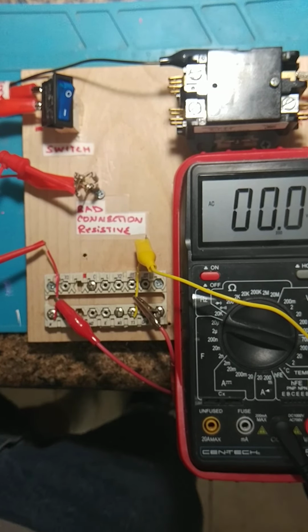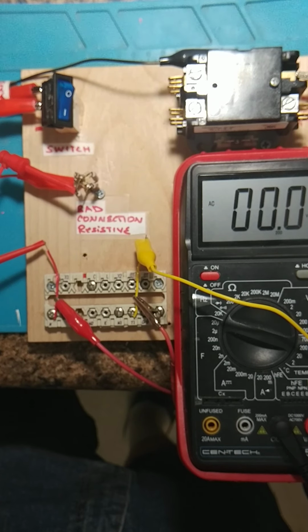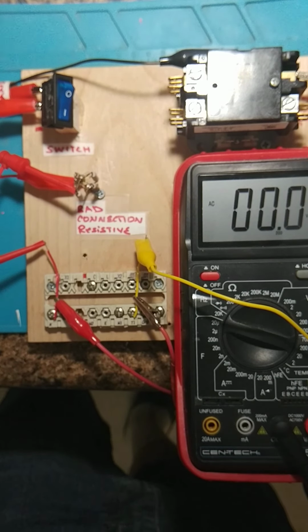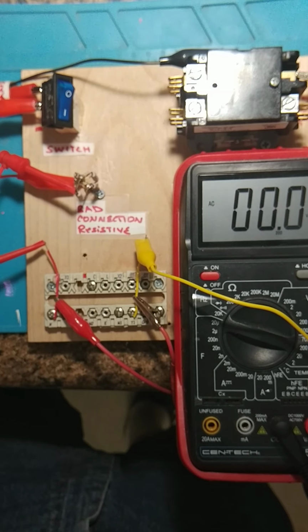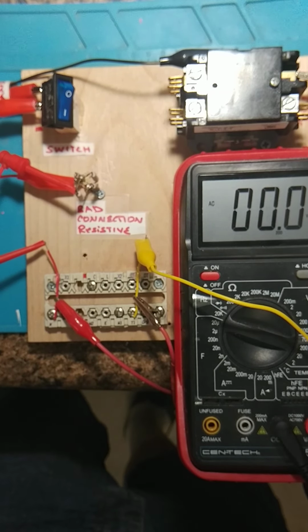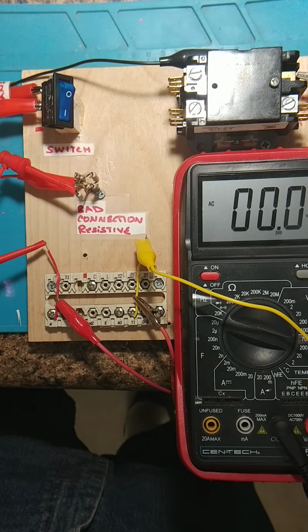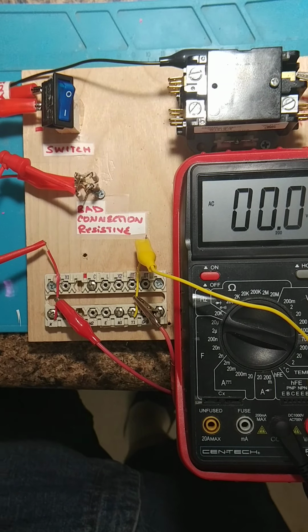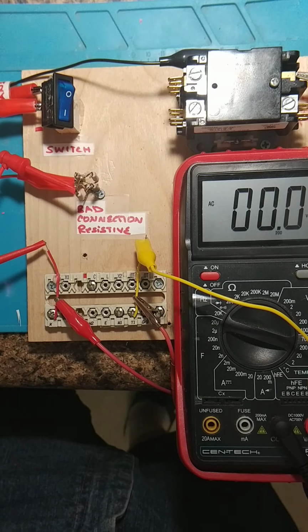Usually this is going to be where a lot of times thermostat wires get spliced. They may be spliced under the line chase where it comes out to the outdoor unit, where they've just spliced it and just shoved it underneath the line set cover.